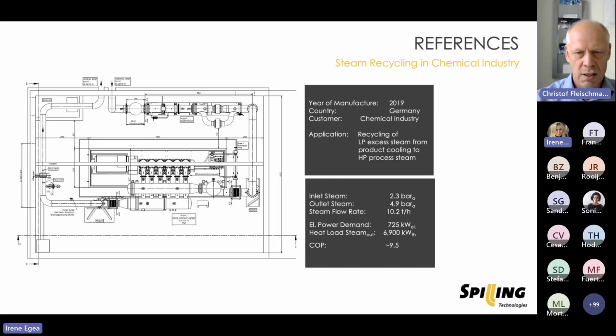And here for this compression, a single stage compressor is sufficient. So all 6 cylinders are compressing in the same way. And since the compression ratio is also not so high, only about a factor of 2.2, 2.3, we get a very good COP factor of about 9.5. Next slide, please.